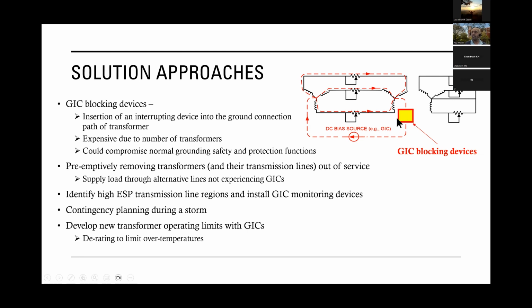Plus, if you do block the flow of this GIC in a particular line, you may inadvertently redistribute the flow of that GIC to another neighboring line. So you block the current here, but it finds its way into another line that you didn't anticipate. And that's the same issue as preemptively removing a transformer and a power line out of service when you know there's a GMD event happening. Can we protect the transformer from damage and take it out of service? Yes, but you might cause this redistribution of GIC.